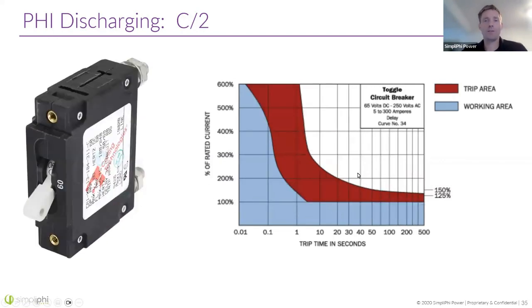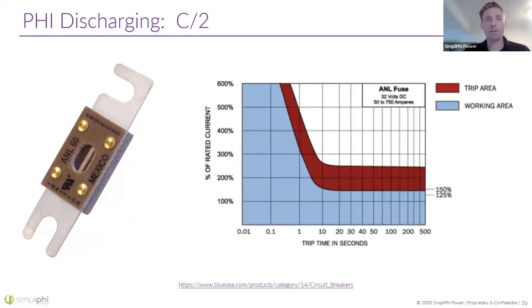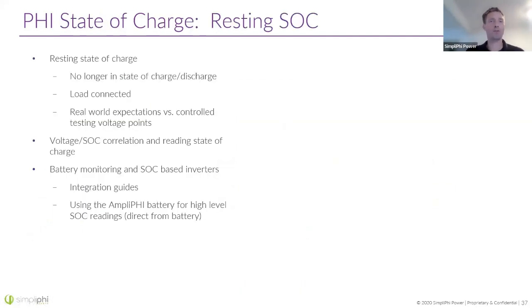So all breakers are a little bit different, right? This is a trip curve on a different 60 amp breaker, and notice that it will trip after just maybe a few seconds. This is a log scale on the bottom. So it looks like maybe about 3 seconds it'll trip at 60 amps. So there is a certain amount of time for a breaker to be able to trip. So pay attention to those trip curves when you are picking out a breaker. Here's another 60 amp breaker, and notice it doesn't even trip until we're at about 140% of that 60 amps. So somewhere around 90 amps over a 500 second range. And I'm sorry, this is a fuse, not a breaker. So just keep those in mind when you're designing protection for your system.